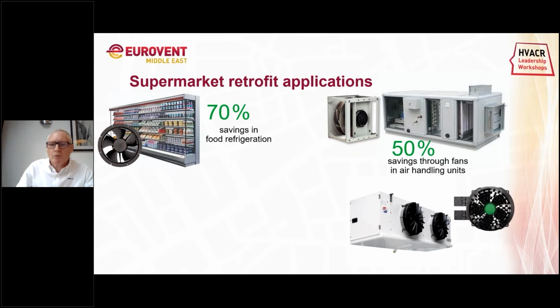Evaporators, yes, we can install EC fans in evaporators. You're really looking at about 30% energy saving. The difficulty with gaining greater opportunities for saving energy is the speed control. Normally, evaporators will run at a set speed.